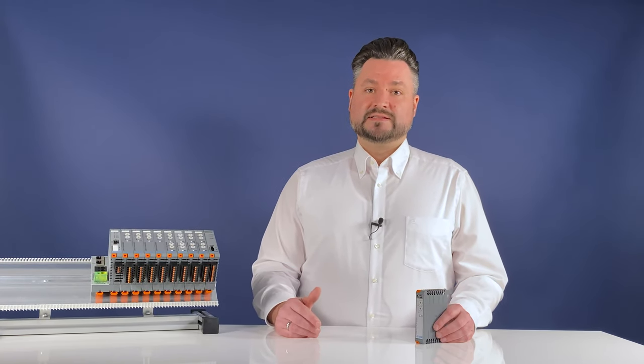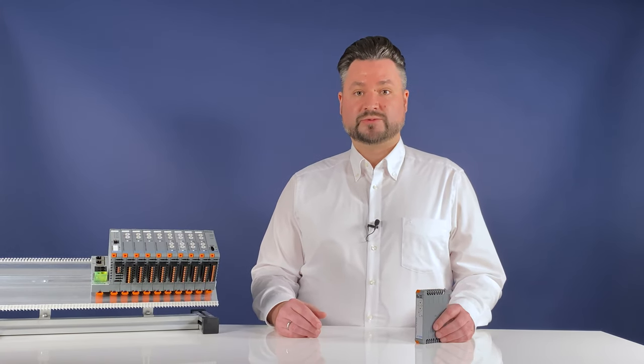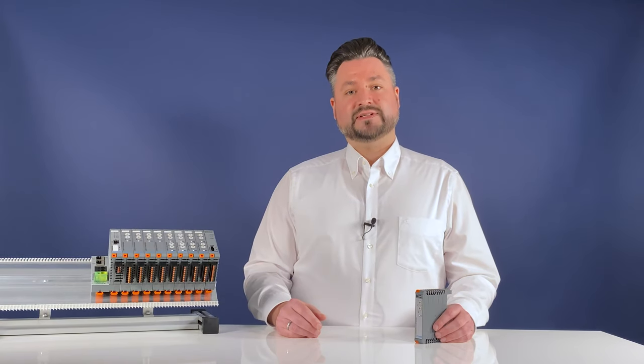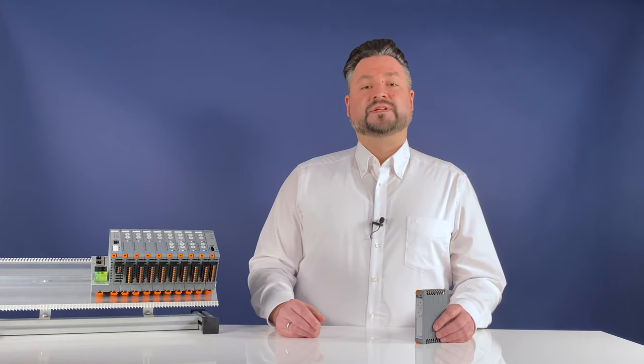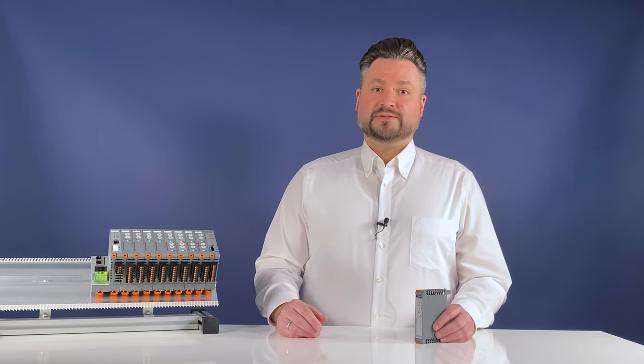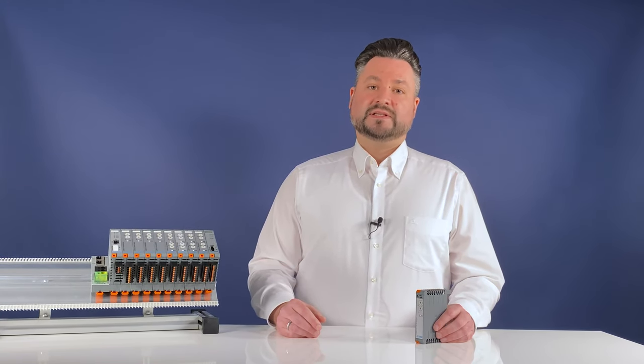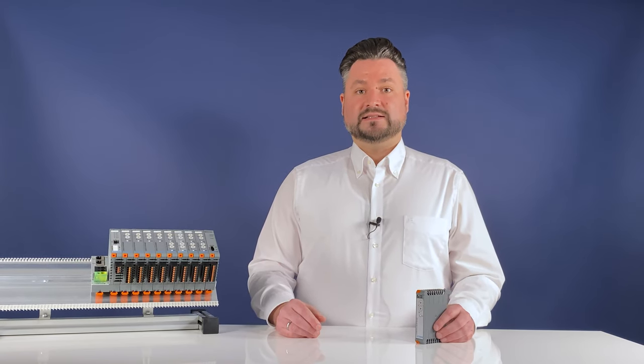The Elkos system has unique properties — for example, the patented analog trigger characteristic, the direct connection of the consumer with positive and negative two pluggable push-in terminals, and in particular, the two-pole shutdown. During two-pole shutdown, the positive and negative supply of the connected circuit is shut down in case of a fault, then electrically isolated.